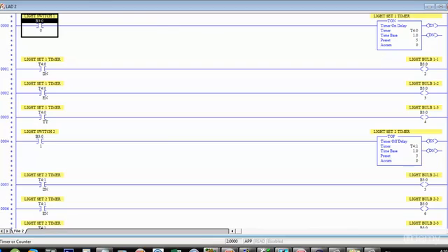We're not really going to talk too much more about the reset, but that works on timers, that works on counters, and that's how the done bit works. So once it times out, it will stay timed out, and that done bit will remain energized as long as everything to the left remains true. And obviously, the energized bit will stay energized as well.